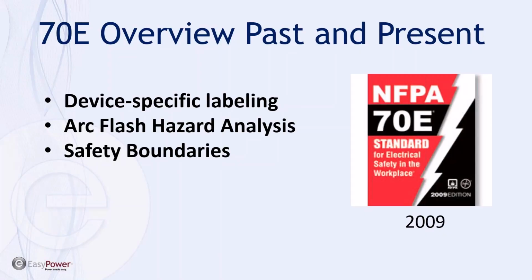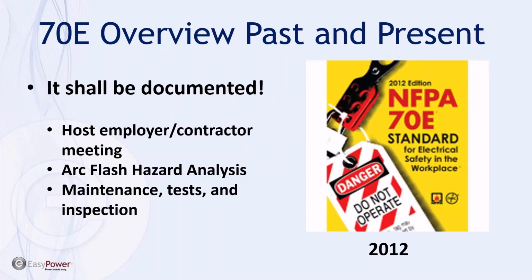And we can cross-reference that example, of course, with the OSHA requirements that a facility shall assess the workplace for hazards. The deliverable to ultimately say that we have assessed the workplace for hazards is the information provided on an arc flash label, as we can cross-reference those compliance challenges. So essentially, doing the arc flash hazard analysis and establishing various worker safety boundaries was part of 2009.